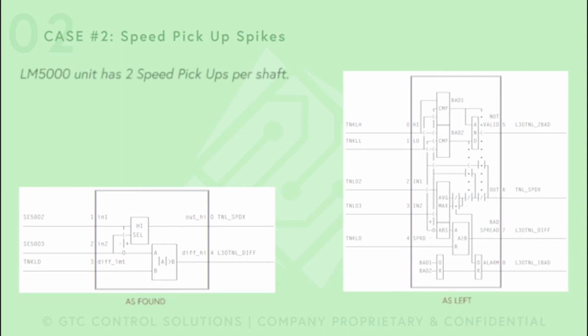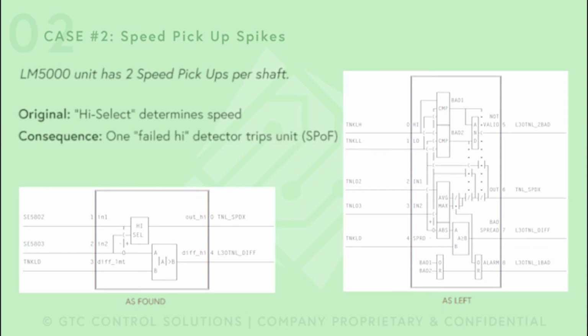The LM5000 has 2 speed pickups per shaft. It's a multi-shaft unit. The original sequencing has a high select block that determines the speed of the unit and also calculates a high differential. The 2 speed pickups are checked to make sure they are not reading outside a specified limit. One fail high detector trips the unit. This is a single point of failure.